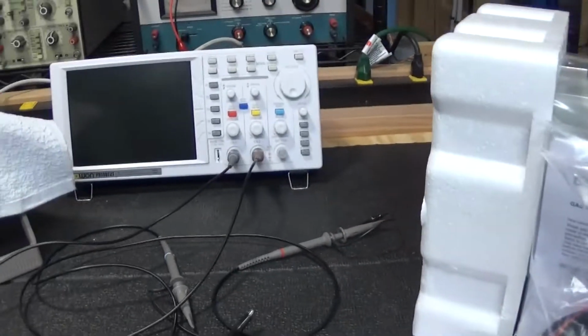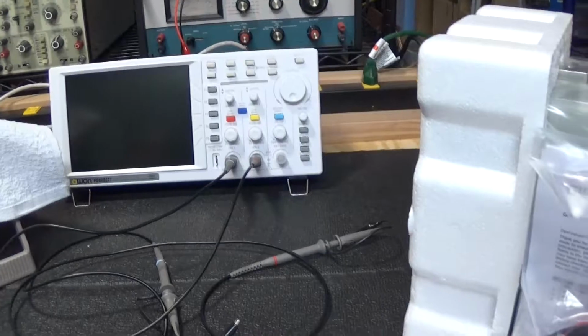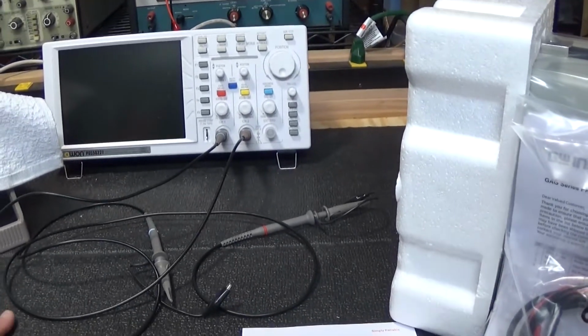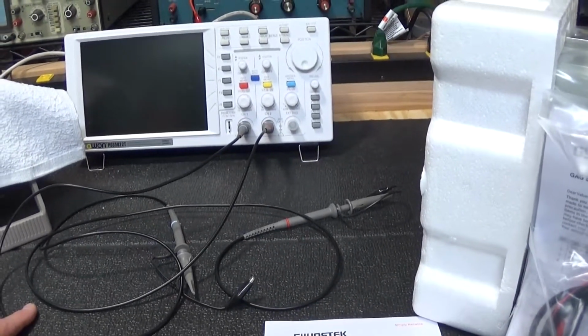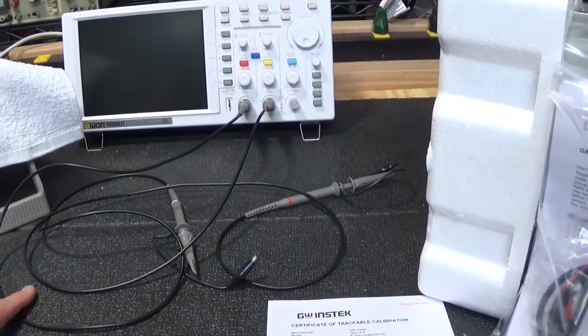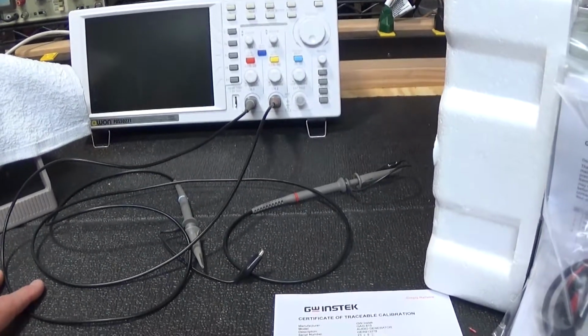But anyway, I realized that those things produce waveforms that, as a matter of their output, have high THD, relatively speaking. In other words, in the range of 0.1 to 0.4%.